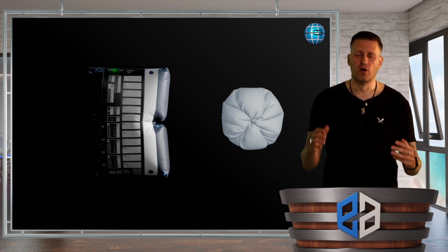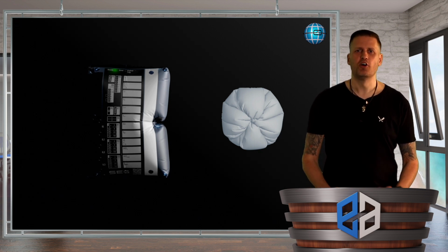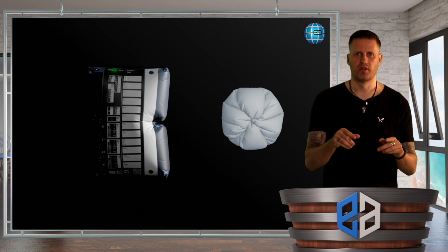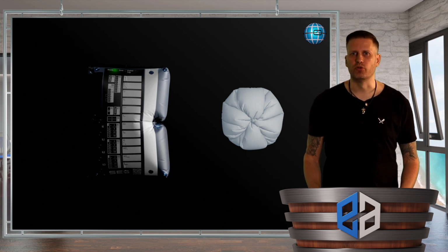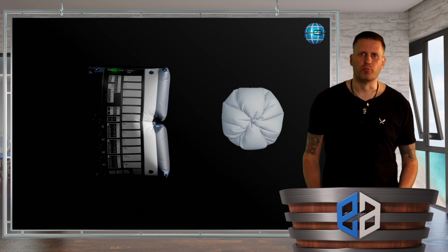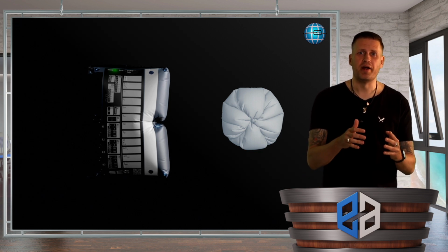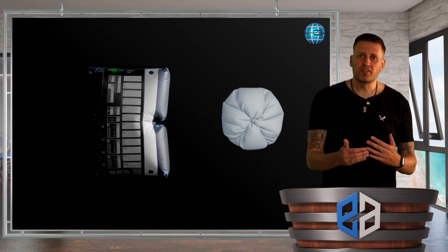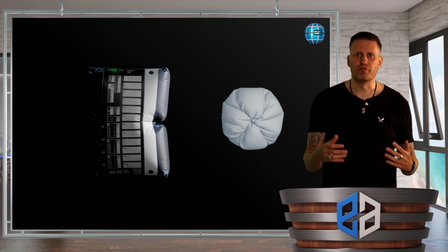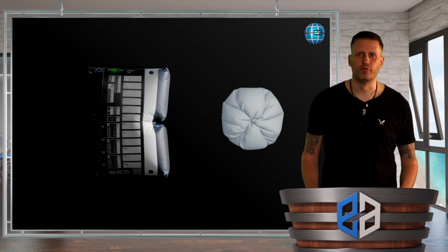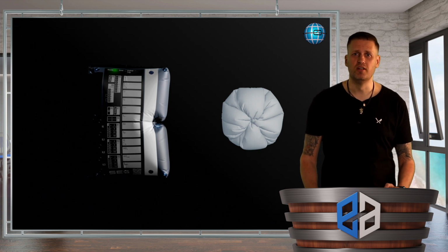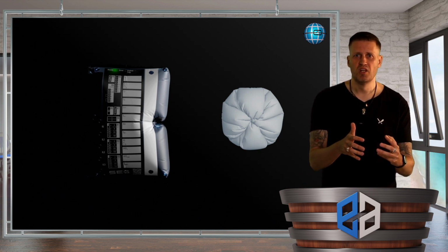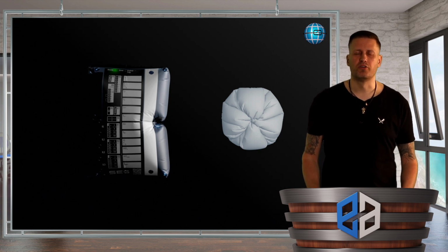You all know this from your lovely Windows computers. And only now, after this wake-up process, is the relay able to make the protection decision and to trigger a possible reaction. And this is exactly where the hamster starts to limp. The faster a CT-powered relay boots, the faster it can react to a switch onto fault event. And now imagine that there are CT-powered protection relays on the market that come along with startup times in the double-digit second range. In this case, you can forget about the protection system and just call the fire department in case of fire.